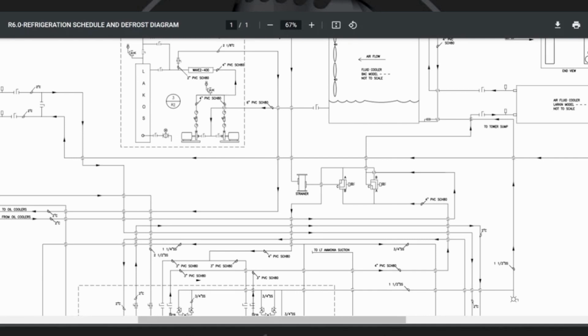Okay. Interestingly enough, there were absolutely no issues. Really? I don't know if you guys have read the building code, but if you read the building code, there is no prohibition of using ammonia. You can use it in a commercial building. You couldn't circulate it down to the cases. But if you have a properly vented machine room, and if you follow IIAR standards, there's no reason you can't use ammonia anywhere. Okay.